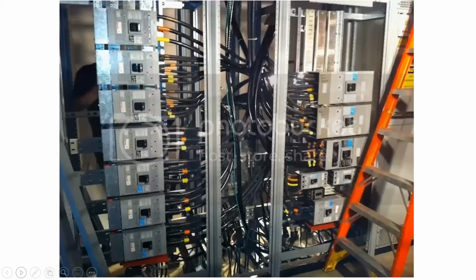So, visual. What's visual? You got to get those covers off. That is probably one of the number one or number two most dangerous things when you look at NFPA 70E, taking bolted covers off of live gear. And why is that? You drop them, and they fall this way, this way, this way, a million times. But if I've got live gear, guess which way it falls? It goes right into the gear.